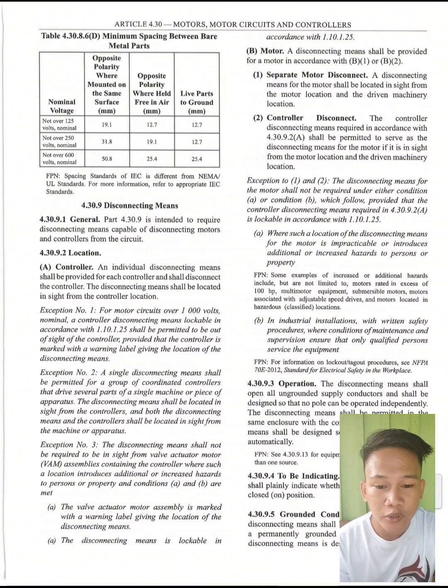4.30.9.1 general. Part 4.30.9 is intended to require disconnecting means capable of disconnecting motors and controllers from the circuit. 4.30.9.2 location. A controller disconnecting means shall be provided for each controller and shall disconnect the controller. The disconnecting means shall be located in sight from the controller location.